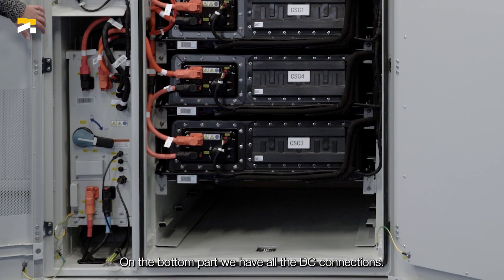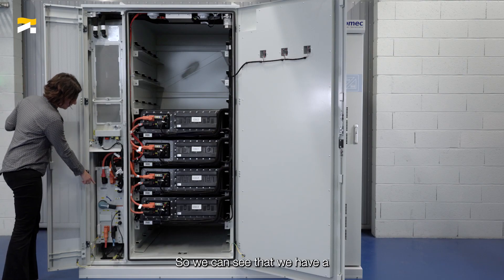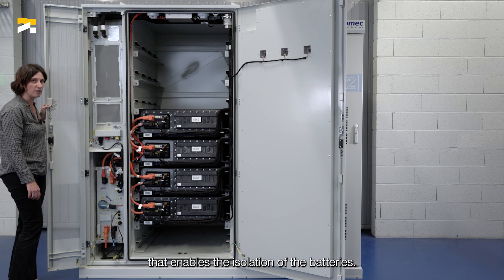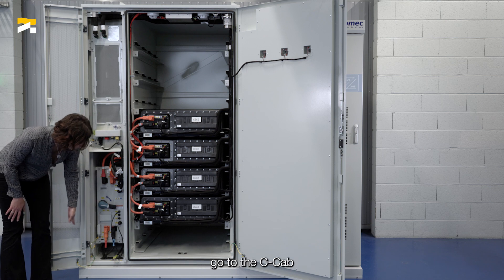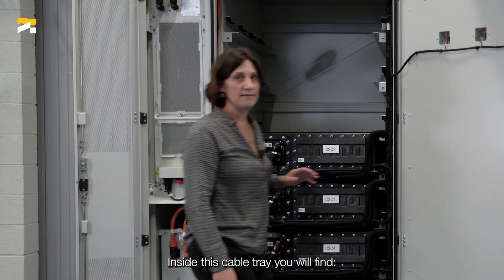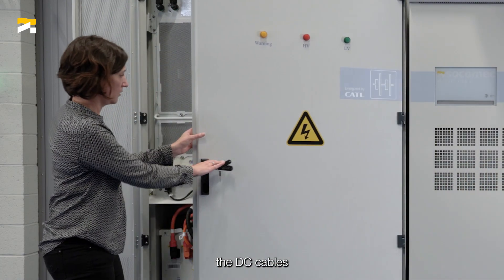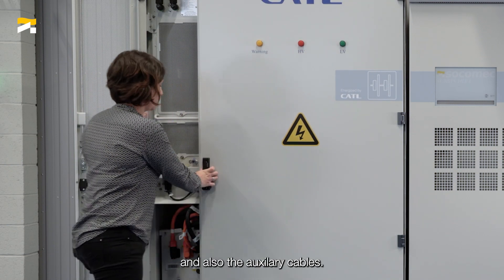On the bottom part, we have all the DC connections. We can see a DC load break switch, SOCOMEC type, that enables isolation of the batteries. Then all the cables go down and go to the conversion cabinet through a cable gutter that we designed. Inside this cable tray, you will find the DC cables, the communication cables, and also the auxiliary cables.